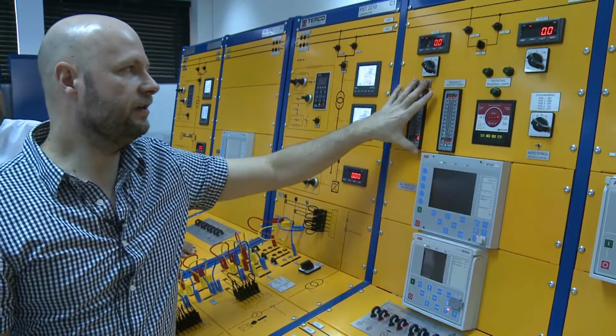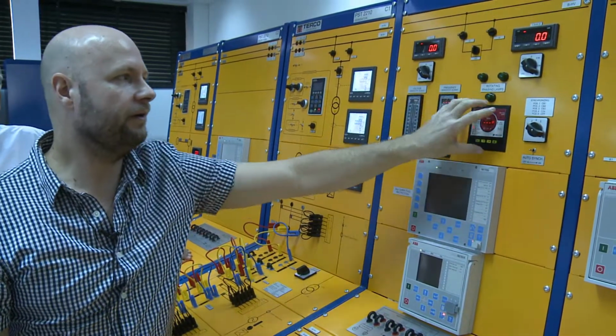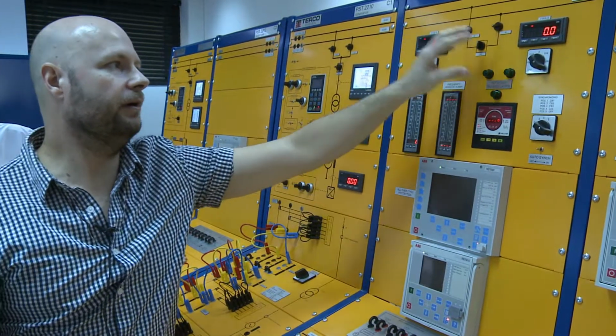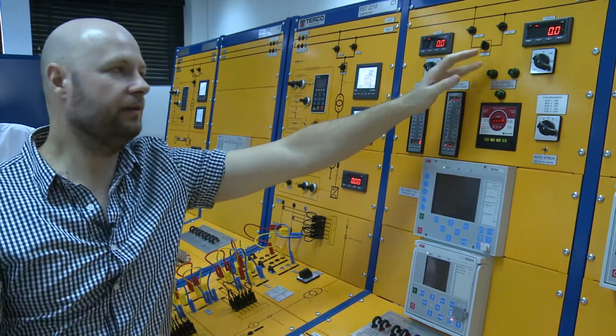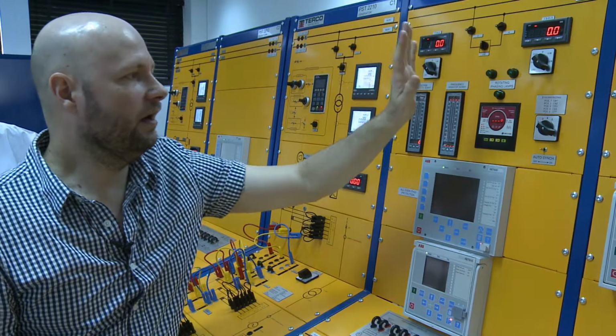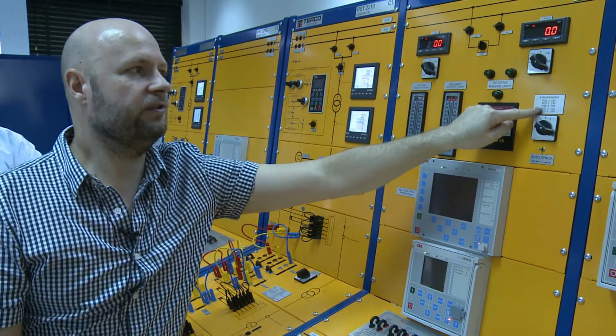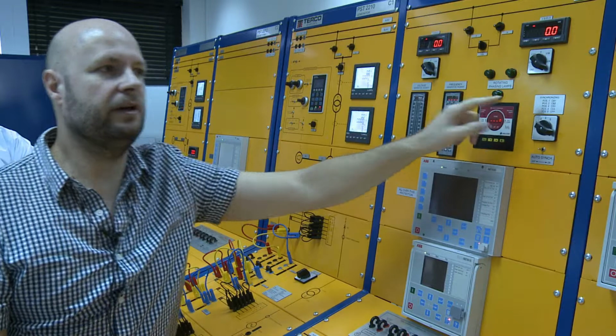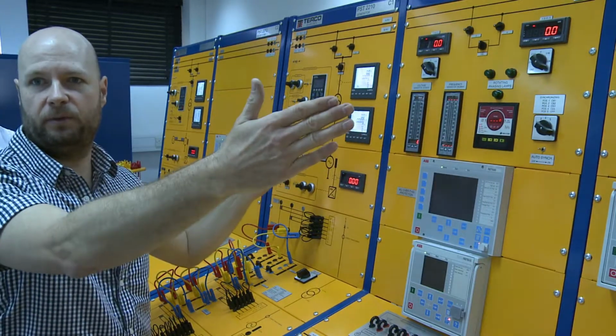This top panel here is all of our synchronization equipment. We have a couple of bus bars, a synchroscope, and rotating phasing lamps to make sure that the sequence is okay. And we have this position selector switch, so we can synchronize at different positions on this module.